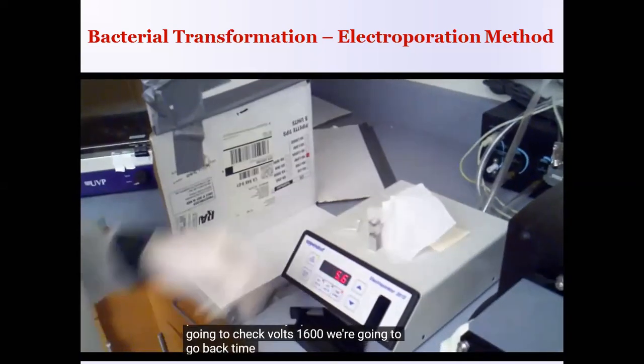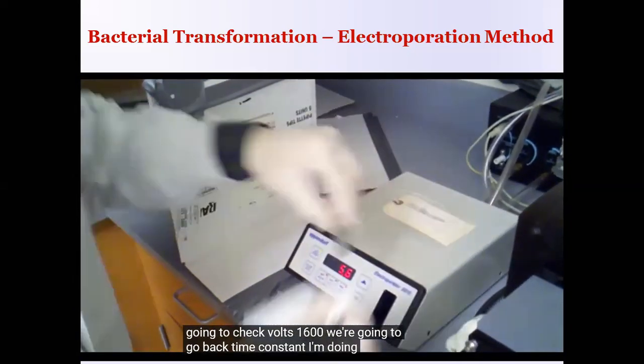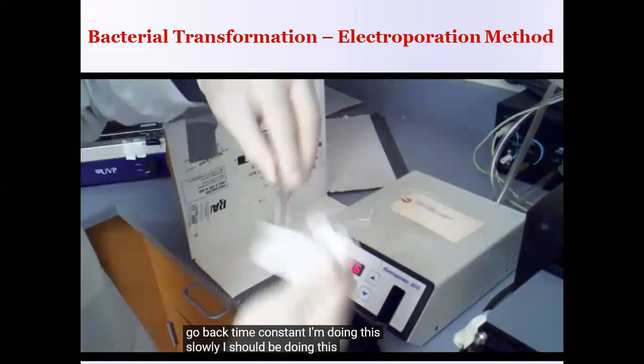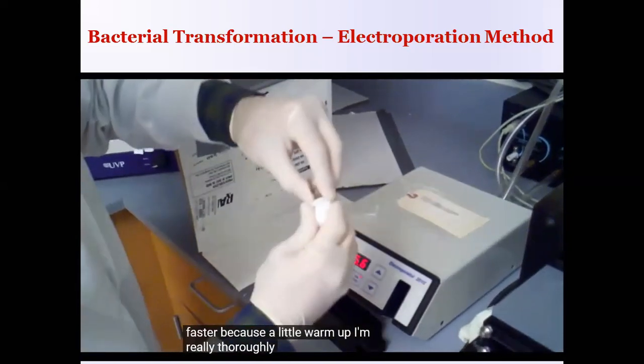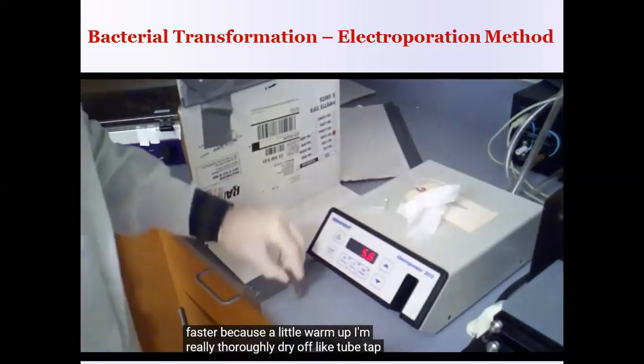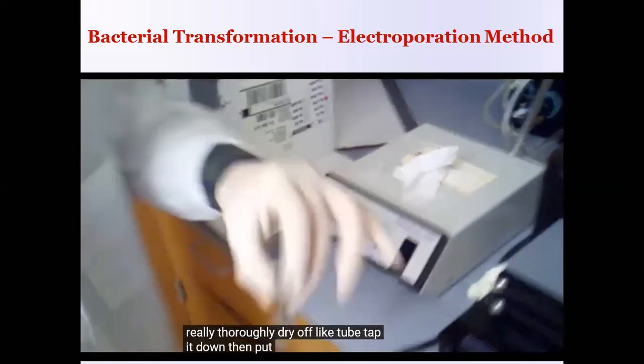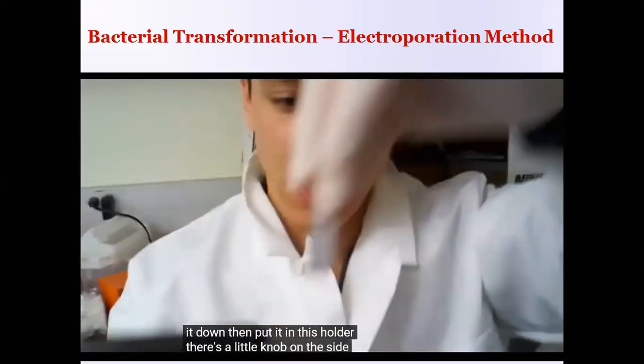We're going to check volts 1600. Then we're going to go back to time constant. I'm doing this slowly. I should be doing this a lot faster because otherwise it'll warm up. I'm going to really thoroughly dry off my tube. Tap it down. And then put it in this holder. There's a little knob on the side. That knob goes down to that little notch.